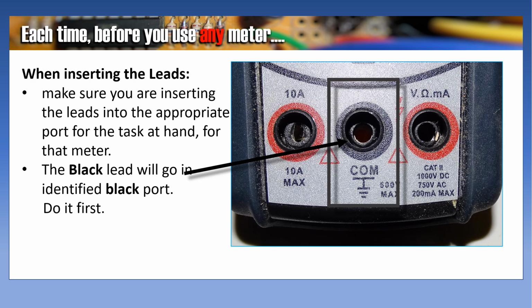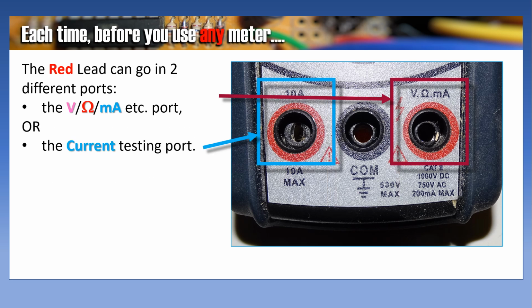When you've inspected them and you're ready to insert the leads, make sure you are inserting them into the appropriate port for the task at hand and for that particular meter. The black lead will go in the identified black port, commonly referred to as common. Do it first. The red lead can go in two different ports. It can go in the volts, ohms, and milliamps port or the current testing port.